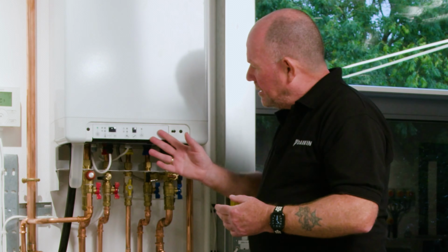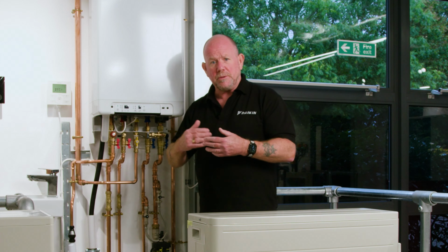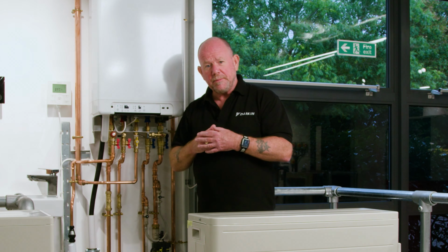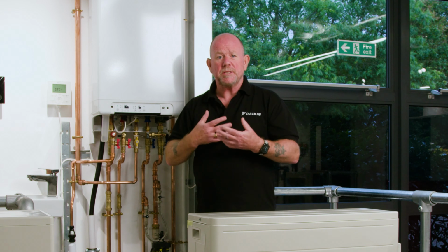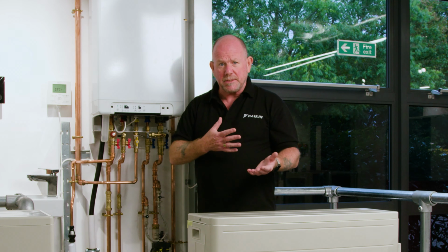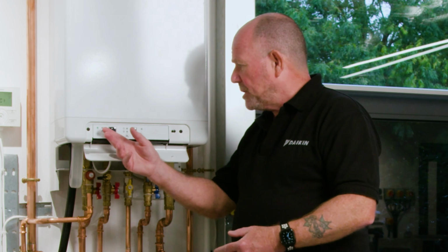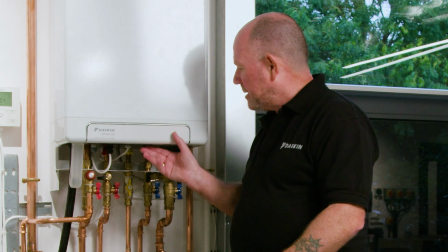As you can see, the boiler control panel has some buttons of its own. The buttons on the boiler are really for the installer. They're used during the commissioning process. We use these buttons to change parameters within the boiler. We also use these buttons to force the boiler to high and low fire for your combustion analysis when you commission the boiler. Clearly, we don't want the end user pushing the buttons on the boiler control panel. So to try and stop this happening, the boiler is supplied with a decorative cover which clicks into place and covers the buttons. Out of sight is out of mind, hopefully.